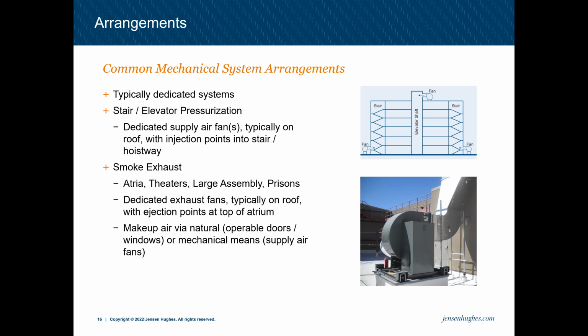They're usually dedicated exhaust fans, but they don't have to be. Some people, for example, the Seattle airport, use their air handling units to accomplish their smoke control needs. This reduces the number of fans that they have to use throughout the roof, and there are a lot of coordination items that they like to use the air handling units for. It does require more fire smoke dampers throughout their system, but it can be used, and usually our requirements in section 909 will transfer over to our air handling units if they're being used for these items.